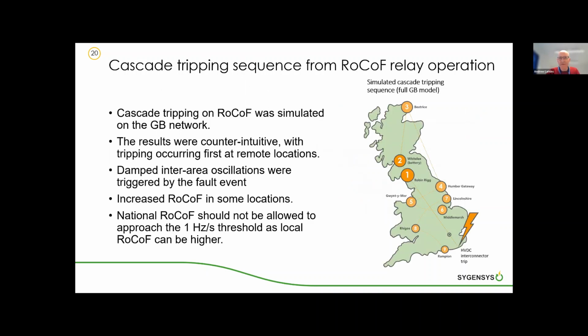So we looked at a full GB network, and we used a built-in existing loss of mains protection relay within PowerFactory and simulated what cascade tripping might look like. Rather than try and reduce the inertia of the network to 2035 levels, we simply set down the level of RoCoF tripping until the first relay operated. And these results are counterintuitive, with tripping occurring first at remote locations. So the case we looked at was for the trip of an HVDC interconnector in the southeast. And what we found was the first site to trip was up here, and the next site a bit further up, the third site was in the top of Scotland, and then the tripping moved further down south.